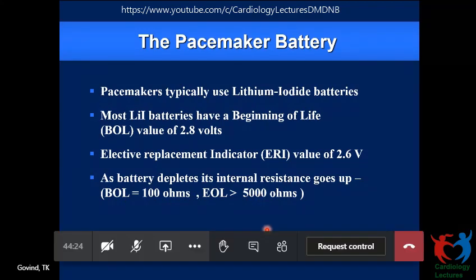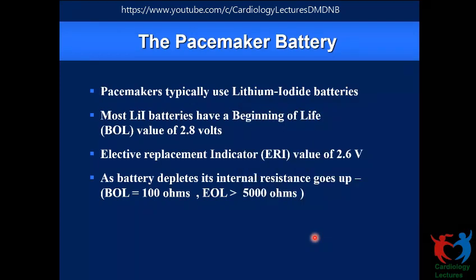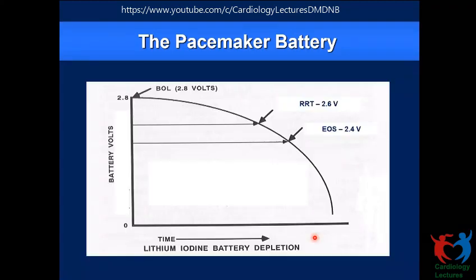But we don't declare ERI based on the battery impedance alone. A lot of things are taken into account, including the voltage and the battery impedance, and the programmer tells you. So it's a good idea to go by the programmer recommendation, assuming that your threshold is good and the output is less than the nominal and not more than that. So that's the battery. This is the typical battery depletion curve. 2.8 gradually drops to 2.6 while the impedance of the battery goes up. And between ERI or RRT and EOL, there is a 3-month guaranteed lifetime. When it reaches EOL, we will not be able to provide any guarantee about the output and hence the capture of that. So it's worthwhile considering replacing between these two. That's an important aspect.